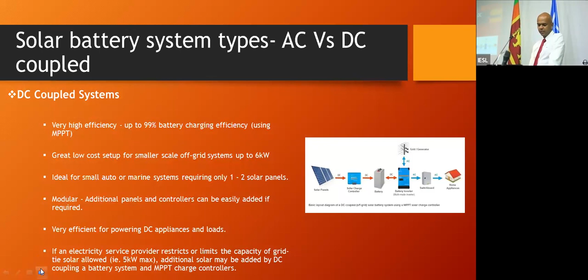Normally, on-grid inverters always check whether it's a real grid - they check the impedance, changes in voltage, frequency, and so on. Any grid inverter will very quickly know whether it's a real grid or an artificial one. But as the doctor explained, with the Fronius inverter you can actually tell it: okay, you have a grid, but the grid isn't infinite, you're working with another off-grid inverter - talk to each other, work together. So that is possible.